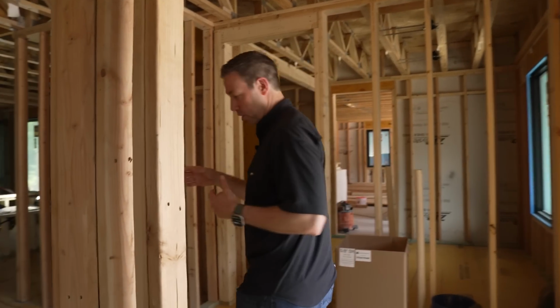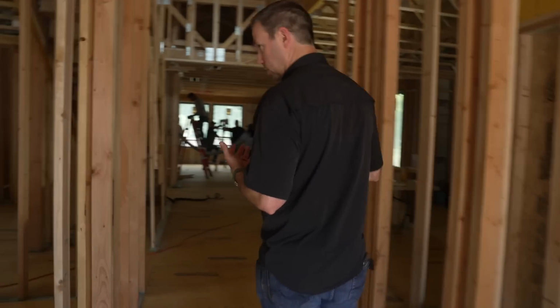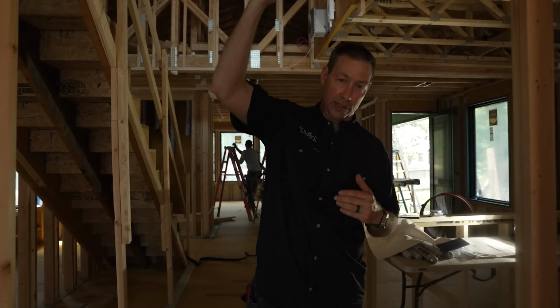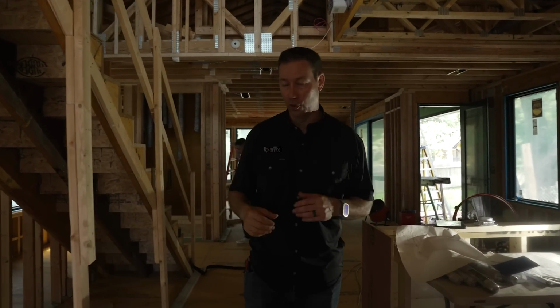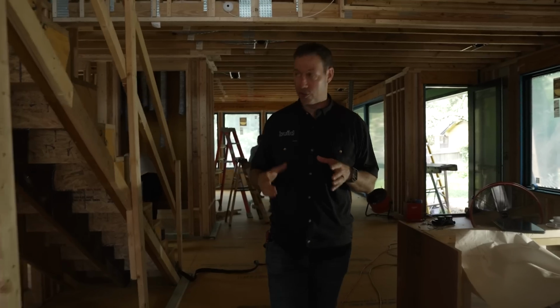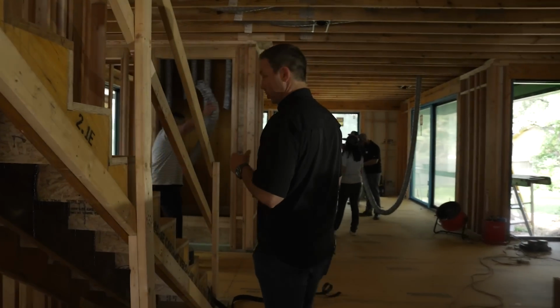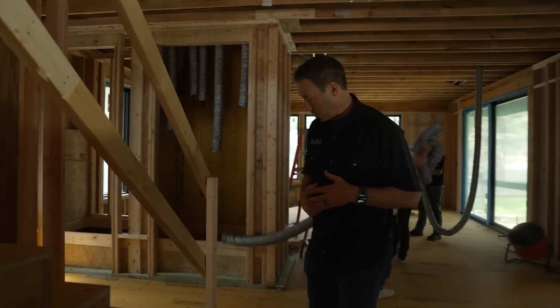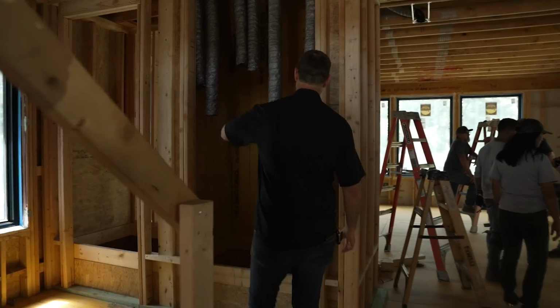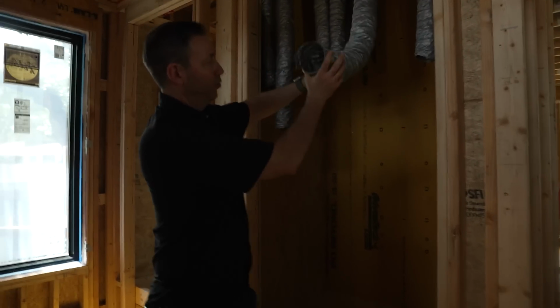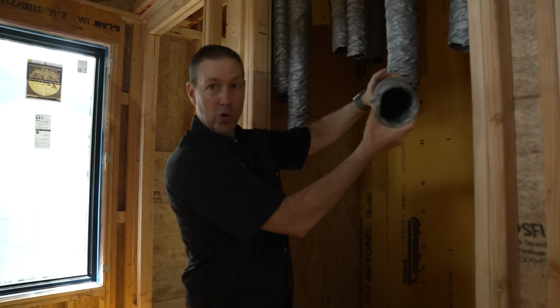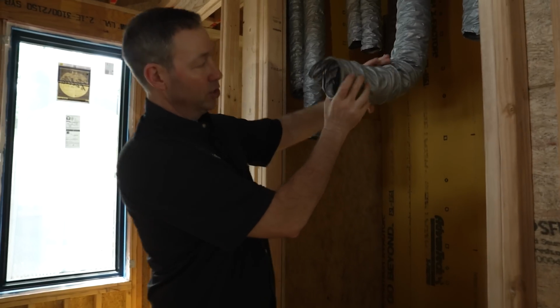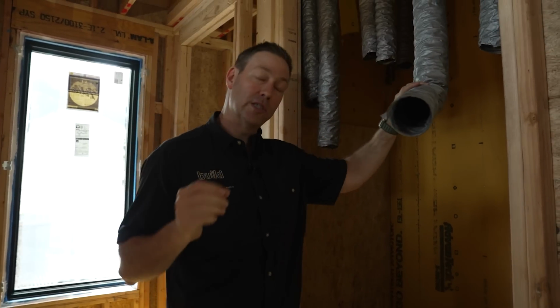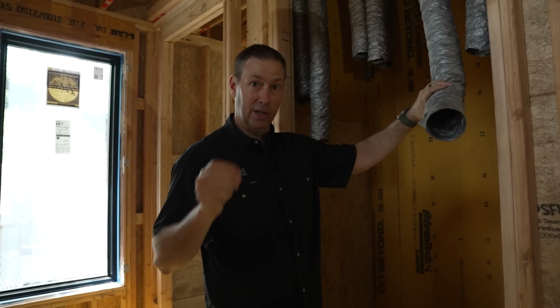We're running something a little different for the ductwork on the first floor. The second floor will be a pretty traditional ducting system, but this gray pipe you're seeing is called Rheia Duct. It's a little different than what you've seen me use in the past. This is a flexible duct, UL rated, and you can see it's non-insulated. It's only meant to be used within the air-conditioned space of the house.